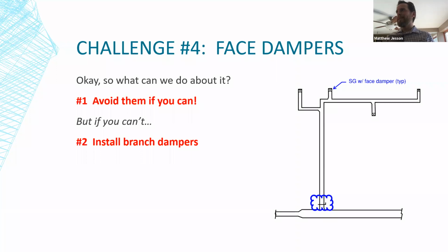So I kind of traced this example out of a prison job. In prisons, of course, access is always going to be a real challenge, and putting accessible dampers in all over the place is not realistic at all. So in this case, we have a branch that goes out to 4 cells, and each one of those has a supply grill with a face damper. Not a lot you can do to get better dampers out here.